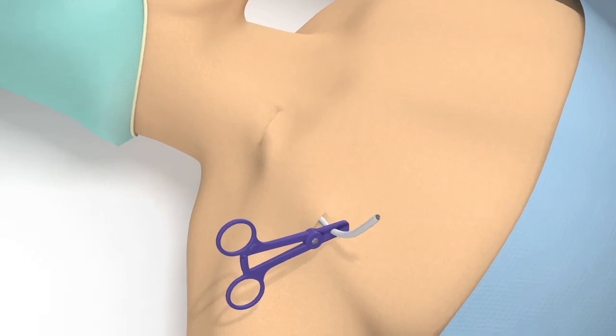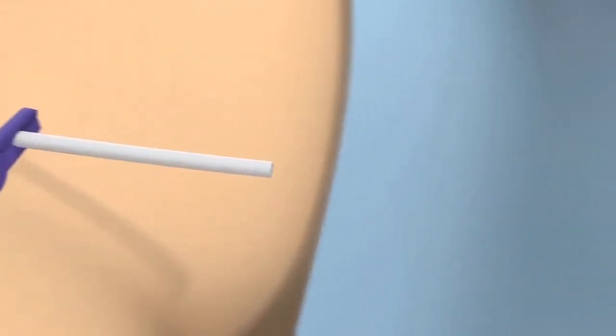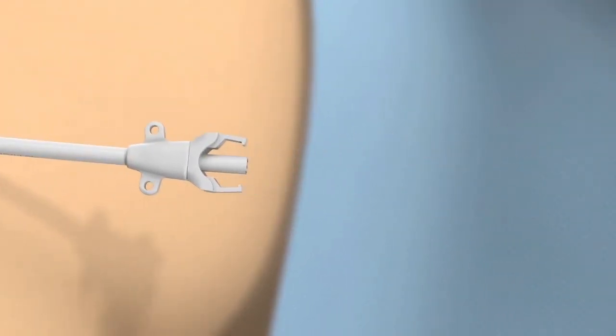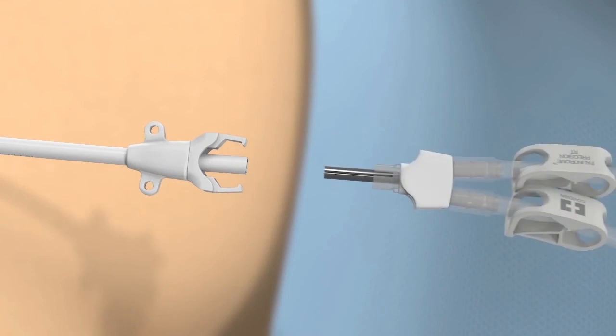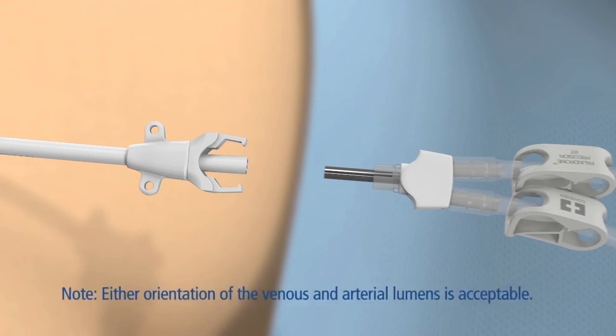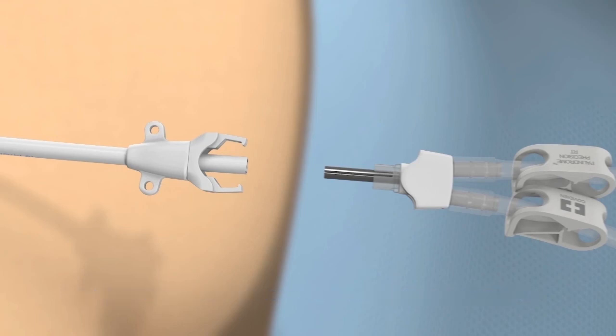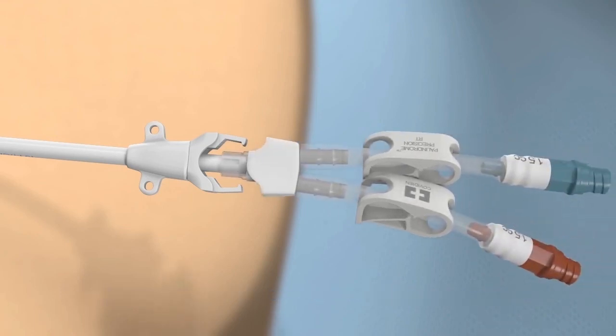Slide the hub snap connector onto the end of the clamped catheter tubing. Align the D-shaped metal tubes of the hub back end assembly with the internal lumens of the catheter tubing. Note, either orientation of the venous and arterial lumens is acceptable. Pinch the catheter and advance it in short increments over the D-tubes and into the locking ring so that the D-tubes are completely covered by the catheter tubing.